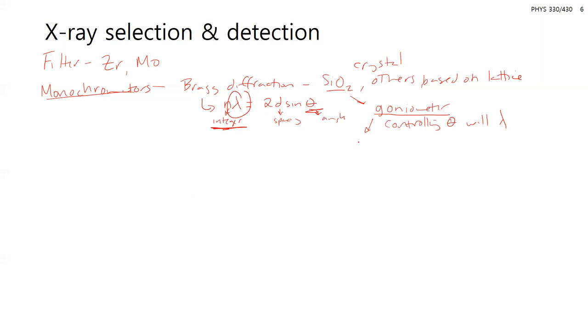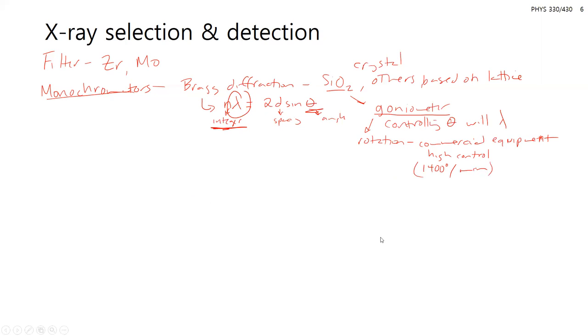Using the goniometer and rotation is key — being able to rotate at a very specific angle and doing this at the right speeds and rates is important. This is typically done with commercial equipment for high control. They might even rotate very fast, 1400 degrees per minute, and having that timing and knowing what wavelength is passing through given a specific rotation takes a lot of optimization, which is why commercial equipment is used.